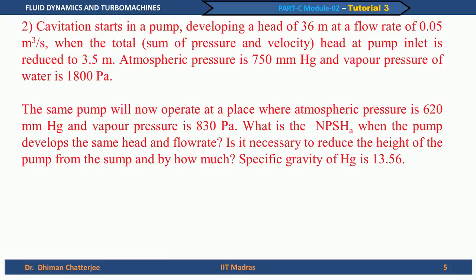The second problem is about cavitation in a pump. A pump develops a head of 36 meters at a flow rate of 0.05 m³/s. Cavitation starts when the total head at the pump inlet — that is, the sum of pressure and velocity heads — is reduced to 3.5 meters. The atmospheric pressure is 750 mm of mercury and vapor pressure is 1800 Pa. This same pump will now operate where atmospheric pressure is 620 mm of mercury and vapor pressure is 830 Pa.